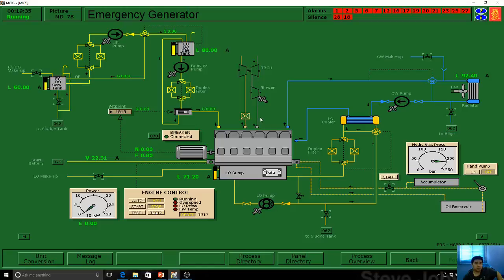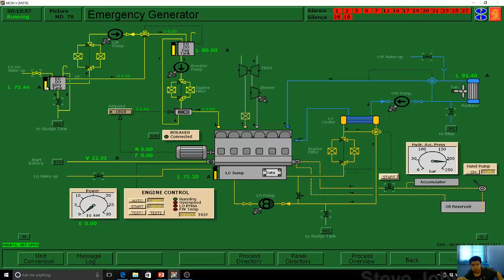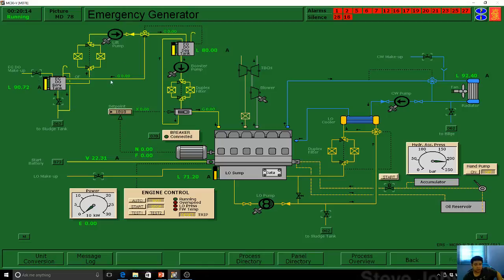It also has a turbocharger and blower attached to the emergency generator. The first thing to do, as I said, is make the fuel service tank as full as possible. I'll put it at 90% — that's good enough. There's a lift pump that transfers diesel oil when it starts. So I've made up the service tank, and we're going to start the generator.